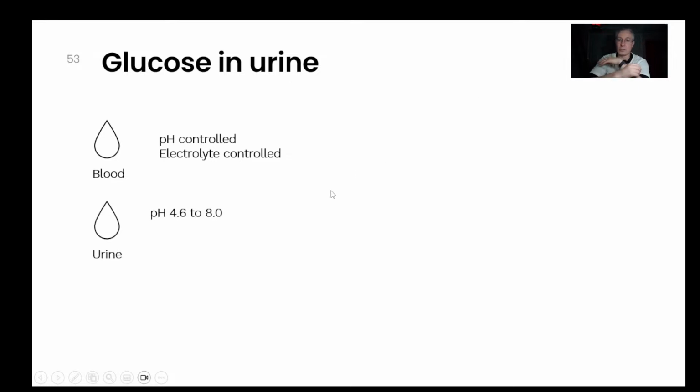Urine has a pH range of 4.6 to 8. So with urine, these are orders of magnitude differences in terms of proton concentration. And then the electrolyte is also changing. It can go from 150 to 300 millimolar, whereas as I said, with blood it's actually quite fixed. The reason I bring this up is because you're asking for an accuracy of 85%, but you've actually got a lot of science to really think through, because you are not dealing with a standard sample, you're dealing with urine. So you really have to think about the science and engineering of actually standardizing that sample before you do the test.